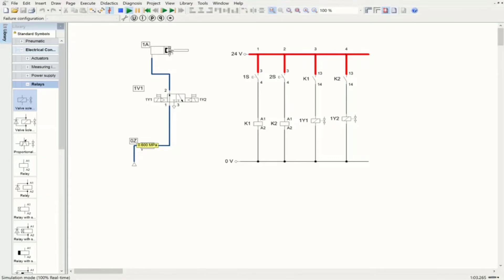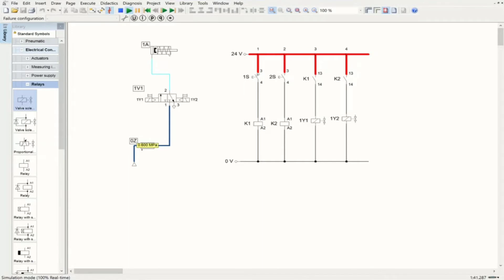The single-acting cylinder is actuated and quickly reaches the fully advanced position. Now if I push 2S, K2 is energized, the relay closes, solenoid 1Y2 is actuated, and the system starts retraction. The retraction process completes successfully. Everything is indirect because there is no direct connection between the switches and the solenoids in the system.